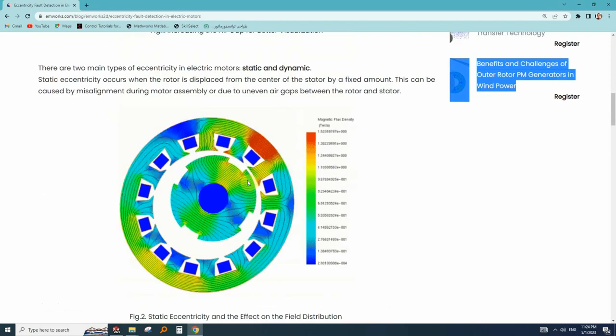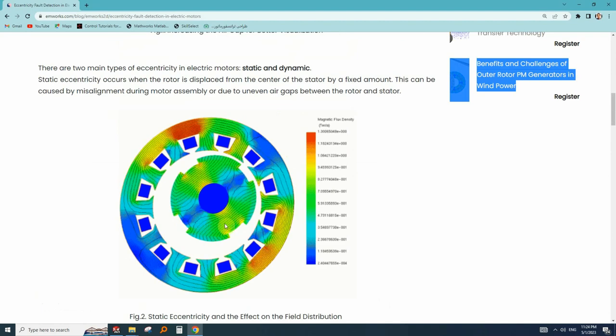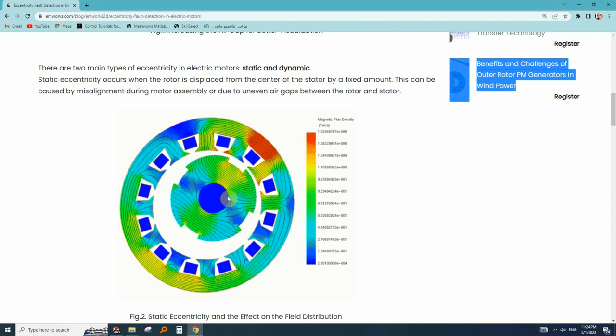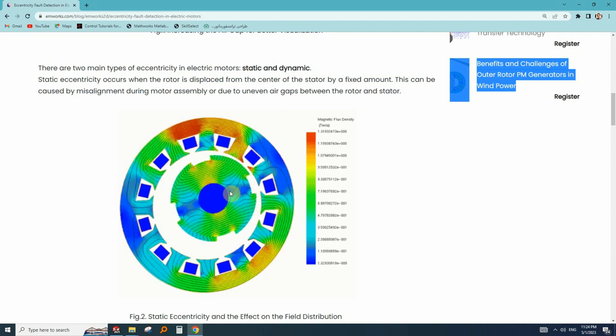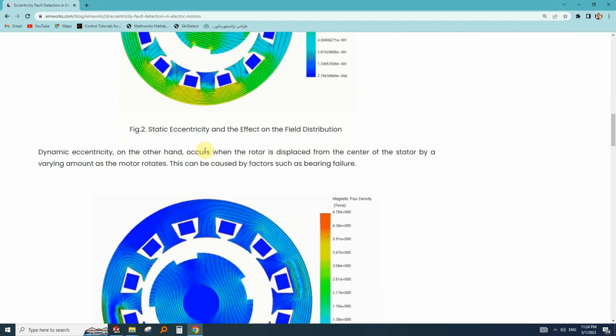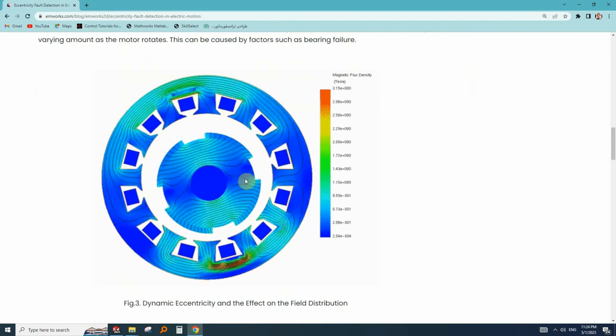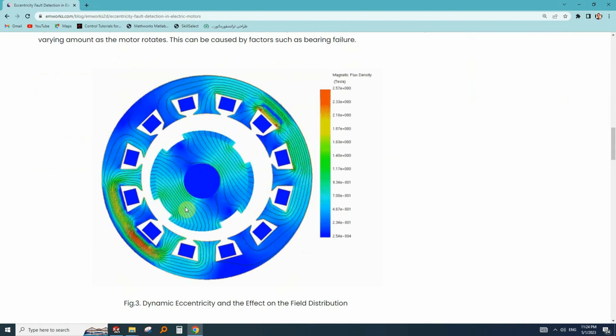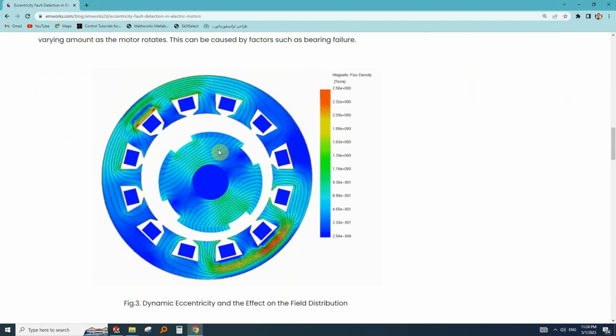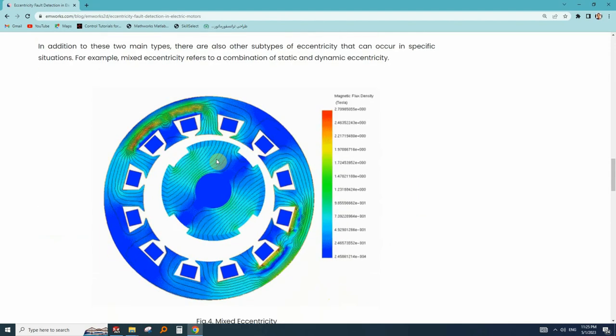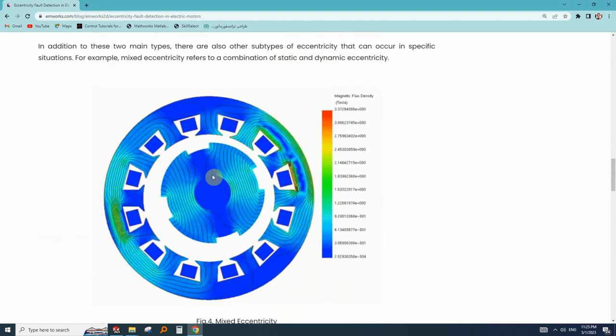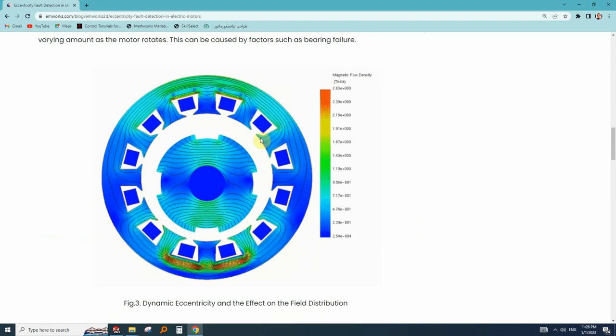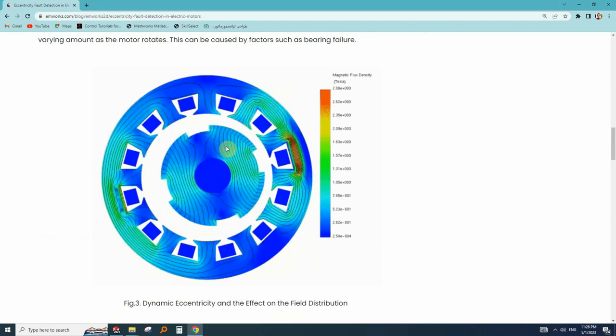We have healthy motor, we have static eccentricity which the center of the rotation is fixed but it's misaligned with the center of the stator. On the other hand, in dynamic eccentricity, the center of the rotation is rotating itself and it's not fixed. And in mixed eccentricity, both static and dynamic eccentricity are present.